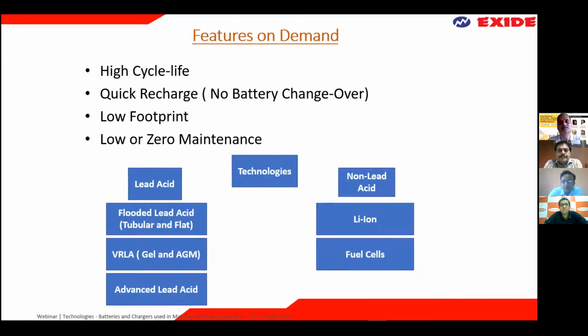Now, when it comes to technologies for batteries, they can be divided into two types: lead acid and non-lead acid. For lead acid batteries, you can use a flooded lead acid battery, which comes in tubular design as well as flat plate design. Then there are valve regulated lead acid batteries, which come in gel form, where the electrolyte is gel, and AGM form, where there is an absorbent glass mat which absorbs the acid. Then there are advanced lead acid batteries. For non-lead acid batteries, the biggest forerunner for now is lithium ion, and then there are fuel cells as well.